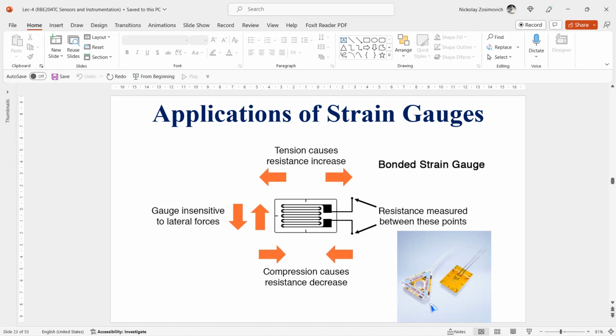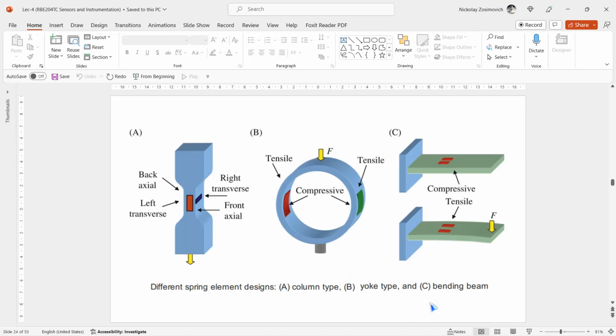So, strain gauges are excellent devices for measurement of force and torque in a mechatronic construction. The bonded gauges are small and can be mounted on almost any part of a construction that experiences a mechanical force or moment. Another approach is to include load cells in the construction. A load cell consists of a metal spring element on which strain gauges are cemented. The load is applied to this spring element.